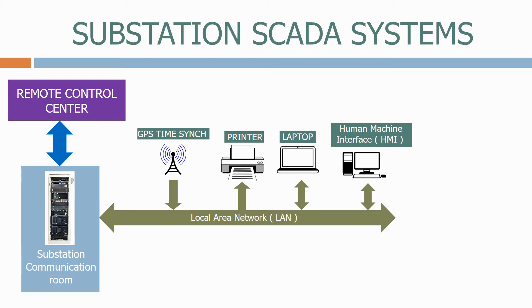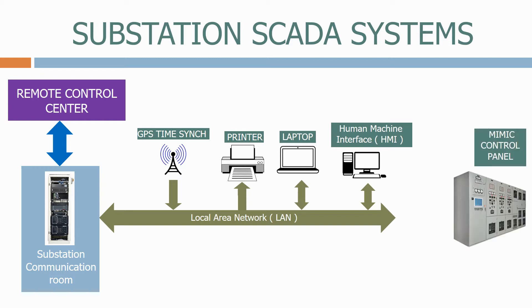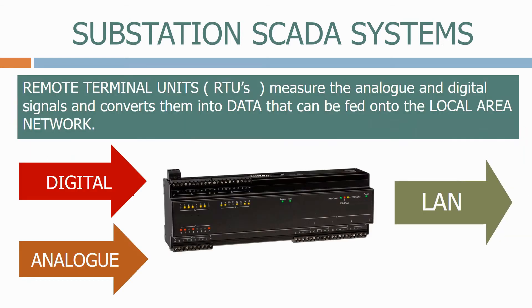We normally have a MIMIC control panel from which the operators can open and close the equipment and monitor any alarms that come up on the station. To connect the MIMIC control panel to the LAN network we use a Remote Terminal Unit or RTU. Remote Terminal Units measure the analogue and digital signals and convert them into data that can be fed onto the local area network.